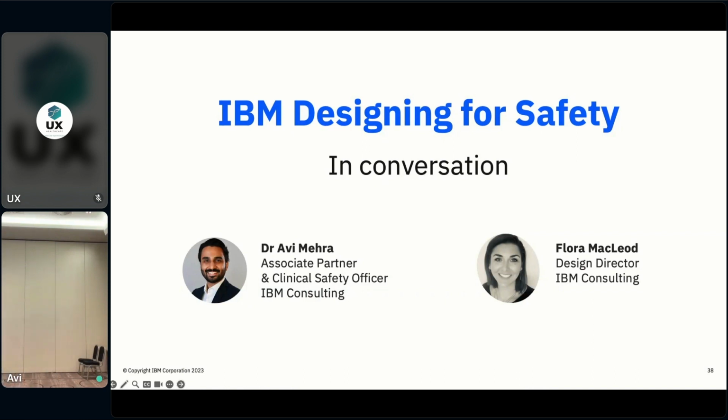And what we'll start with, I will often give a brief overview of clinical safety for 10 minutes, because most people have never been in a workshop before and have no idea. So just an explanation of why we're doing this, what we are trying to assess, and the standards. Then we'll often ask, usually the designer or developer, to do a walkthrough of the system end to end. Whatever that is, take us through the solution, and then we break it.